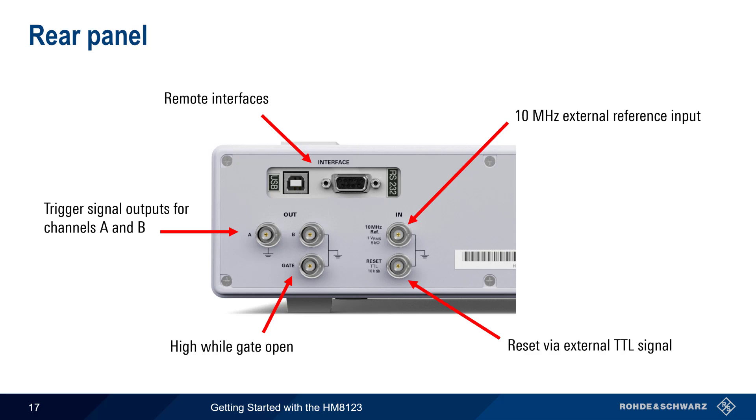The last topic is Rear Panel Connectors. The HM8123 comes standard with USB and RS232 for remote control, and an optional GPIB interface is available. The HM8123 can accept a 10 MHz external reference input, and an external reset connector can be used to reset measurements in the same way as the reset button on the front panel. The gate connector outputs a voltage over the gate time, that is between the start and stop of the measurement gate. And trigger signal outputs are provided for both channel A and channel B.